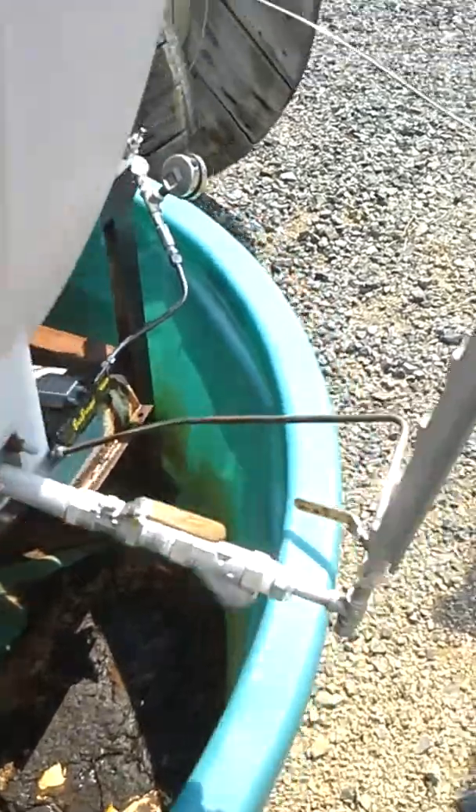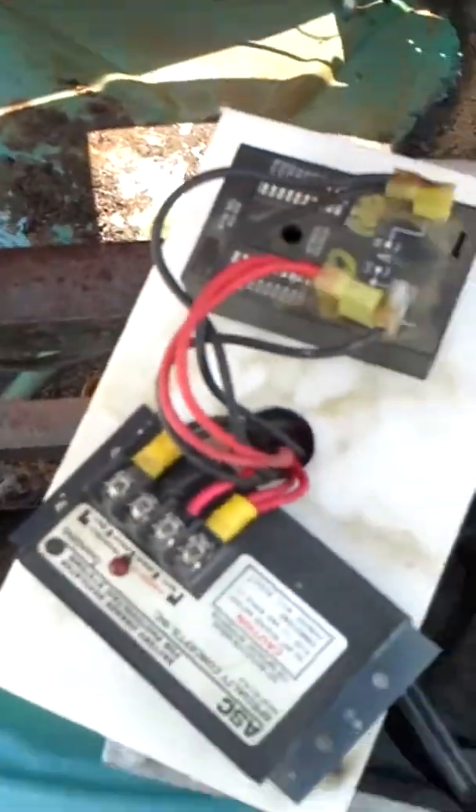Check this out. It's a sun pumper — an electric pump. This is about the 10th time in the past month I've had this problem. The solenoid will click, the pump won't kick on. You can see that little red light come on but nothing happens. I suspect it's the same problem we've had all these other times.